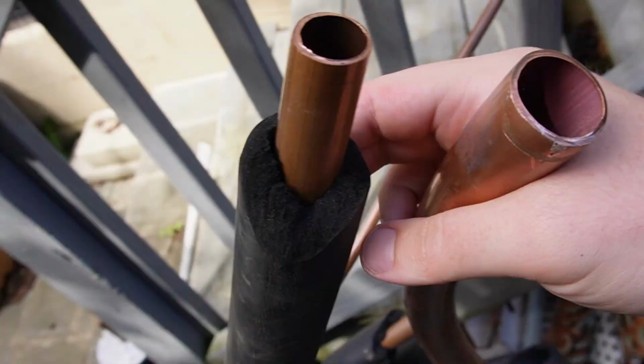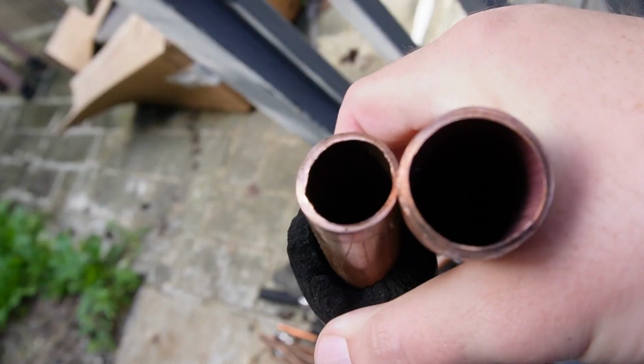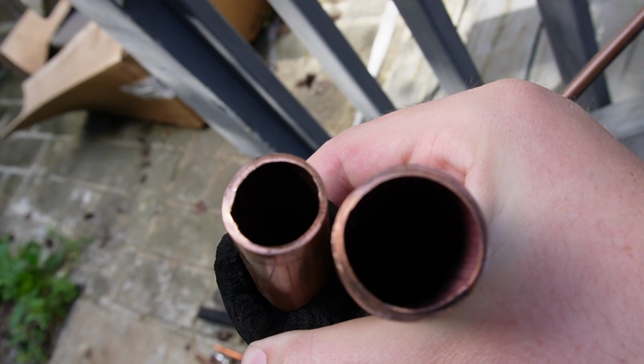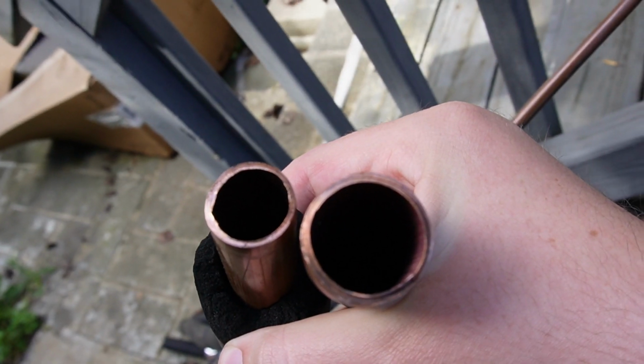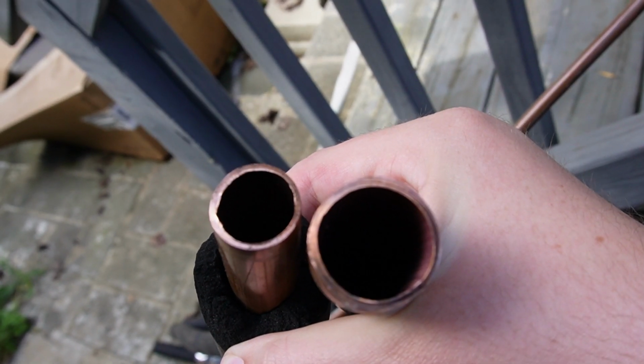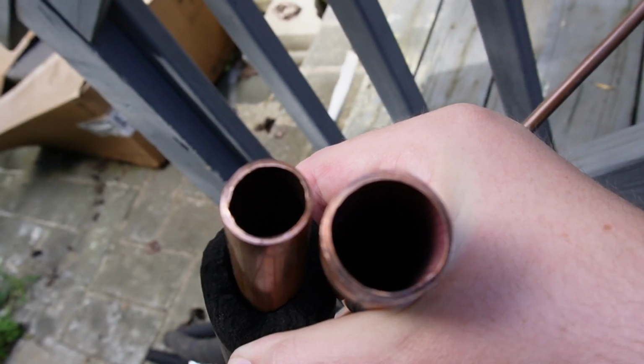What's up guys, I'm here with a little recap. I wasn't able to capture the line set replacement in action, but I do have an update here. I wanted to show you guys the difference in the size that was there and left - original and not replaced with the install - and what we changed and how big it should be. So the line set was kept original at 7/8, we changed it to 1 1/8, and here's the difference side by side, old versus new. So here's the old one on the left, and that is the 1 1/8 there. So could you see how that would cause issues not being at manufacturer specs?